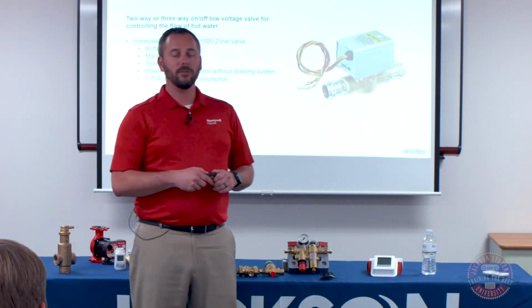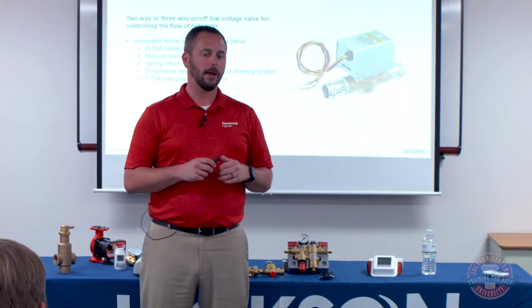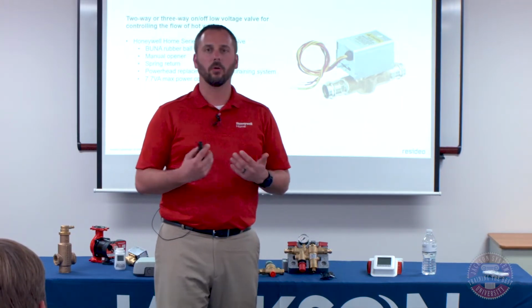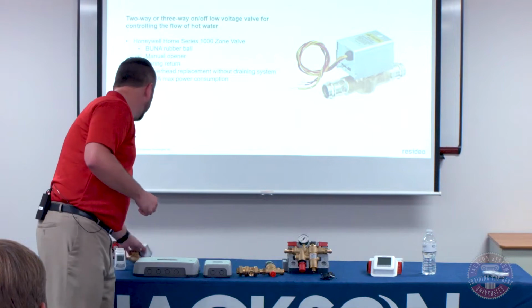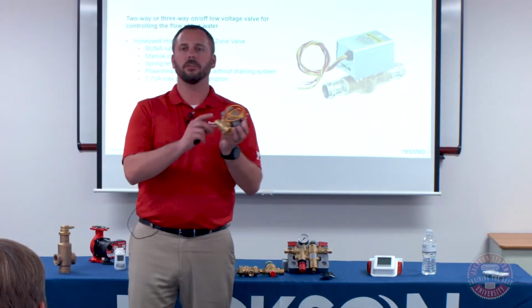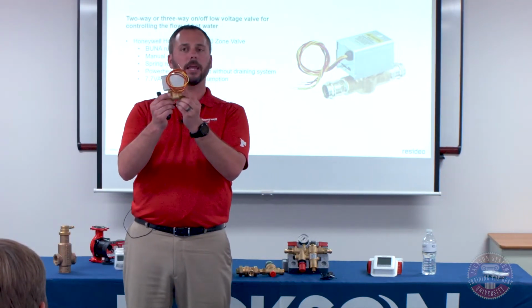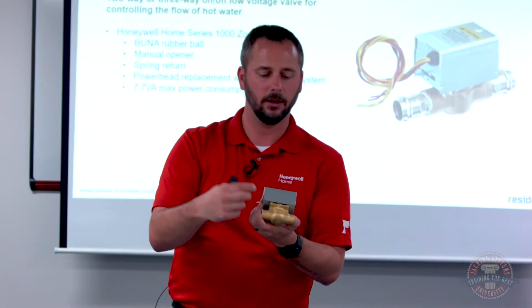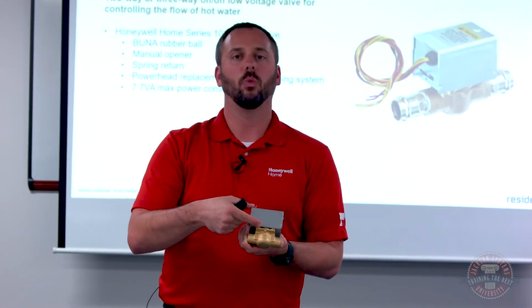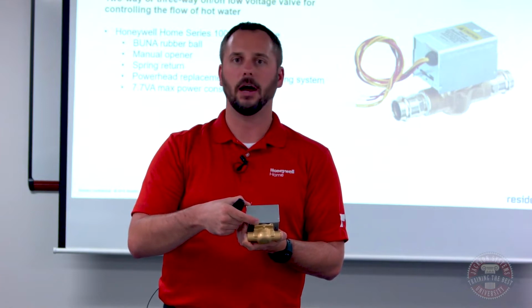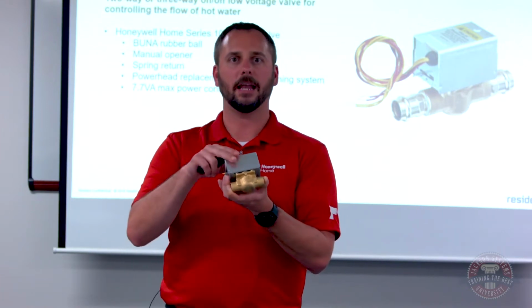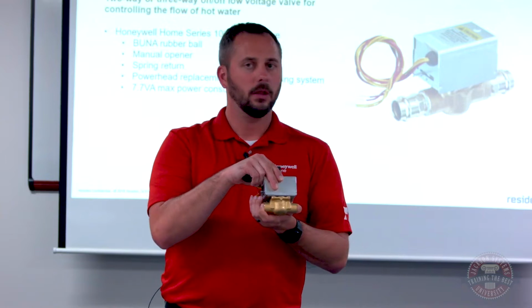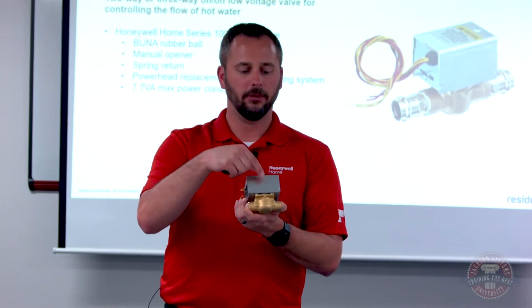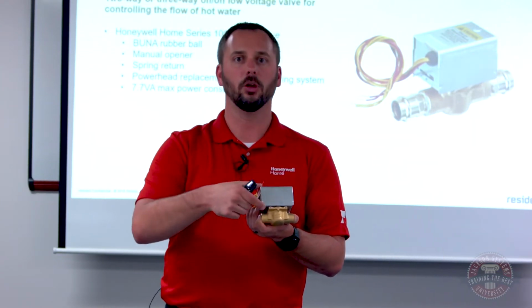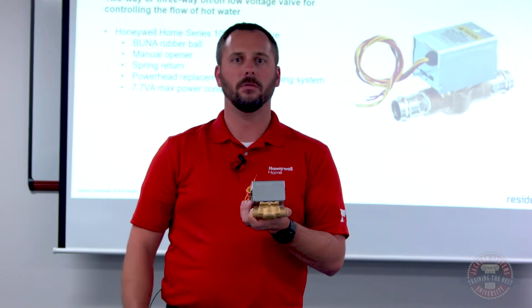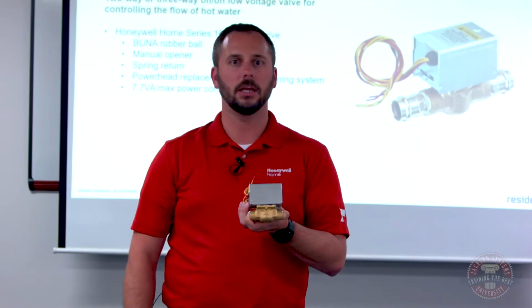So we've got 2 different series of zone valves, and I'll talk about both of them. The first series is our 1000 series zone valve, which consists of mainly 2 components. You have a valve body here, as well as a motorized power head on the top. We sell them packaged as one unit. We do sell replacement power heads, which is the aluminum-looking piece on the top that can be dry fitted onto a valve body without any issues.